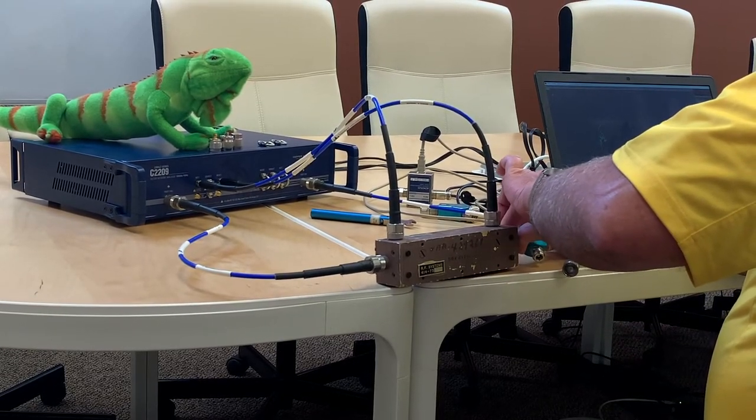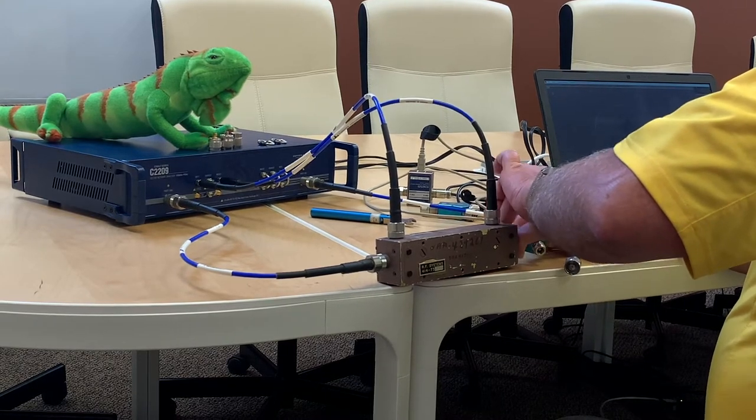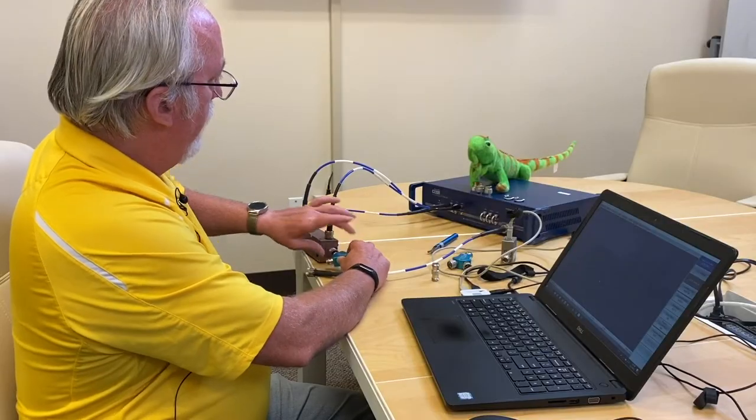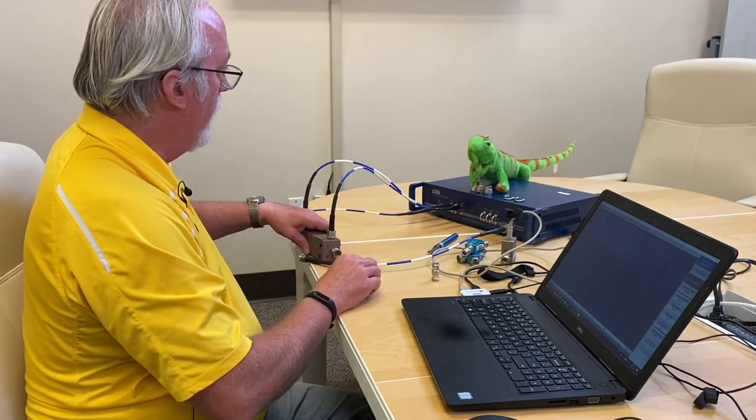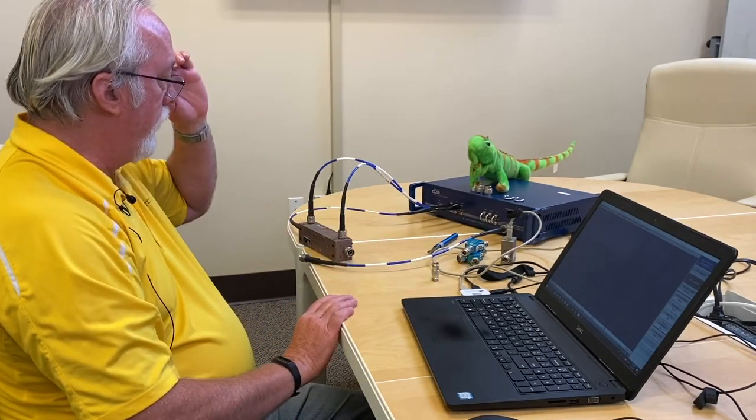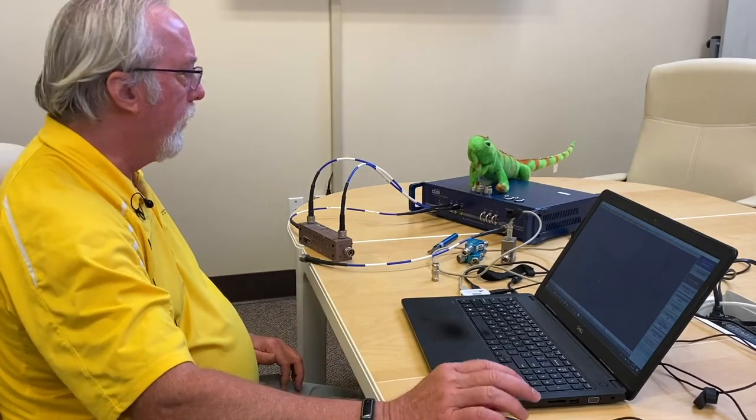As you might know, an open on Smith chart is here at the very right-hand side but a CalKit open looks like an arc, a clockwise arc. It starts at a very low frequency, it looks just like this theoretical open. But there is an internal delay inside the open so you get this arc on the screen. This is typical. So I can tell that my calibration is good. If it had gone many, many times around the screen then I would have a problem.